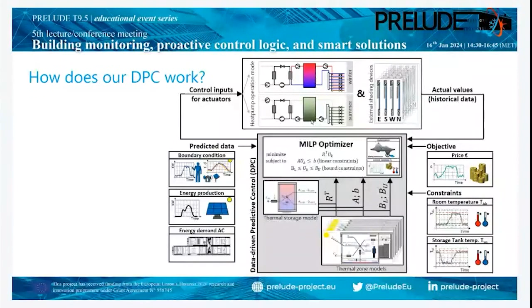In this slide, you can see which control inputs we used in the winter operation mode. We get a switching signal for our heat pump, which is reversible. We can load the hot water storage tank with the heat pump, and the operation schedule we get is for the next 24 hours.